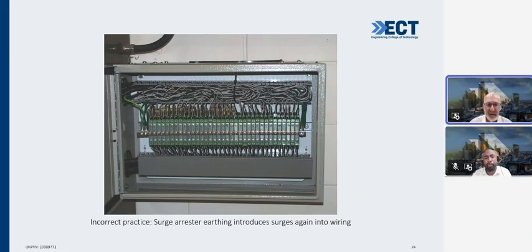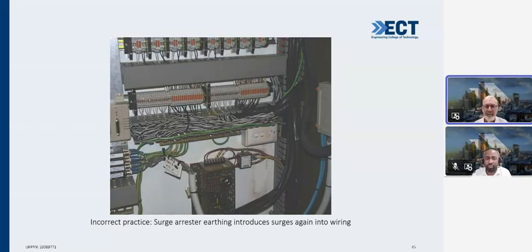Here again, look at the top of this surge arrestor - the surge arrestor itself is brilliant, thank you very much for putting those in. But they've gone and mixed all the cable up - the in and out cables of the surge arrestor are all mixed up, so one cable will reintroduce the surge into the other. You need to check this out - I'm very disappointed with this. Same problem here again.